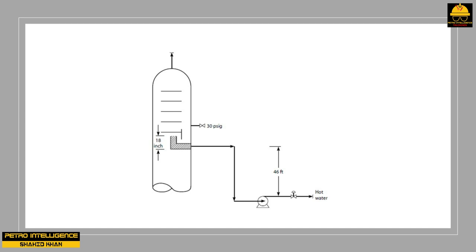The boiling point pressure of the water equals 30 PSI G — the pressure in the tower — so the water draw is at its bubble point pressure. At 36 PSI G pump suction pressure, the available NPSH is: (36 − 30) × 2.3 = 14 feet. This matches the required NPSH at 110 GPM, so the pump cavitates. Yet it seems as if at least half of the 46 feet of liquid head to the pump is missing.